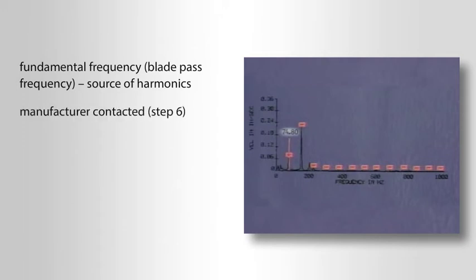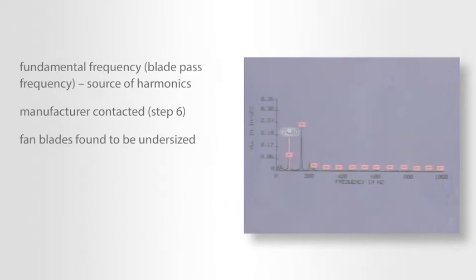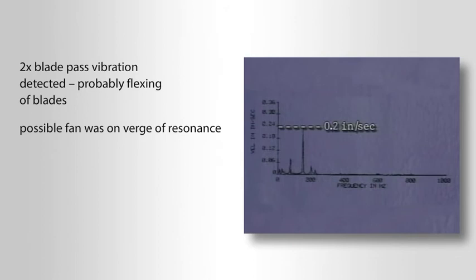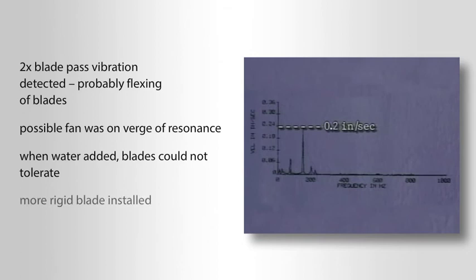Finally, the manufacturer was contacted — step six. Numbers were rechecked and the fan blades were found to be undersized. The two-times blade pass vibration detected when no water was flowing was probably a flexing of the blades. So it's possible that the fan was on the verge of resonance. When the water was added, the blades could not tolerate the force. A more rigid blade was installed.